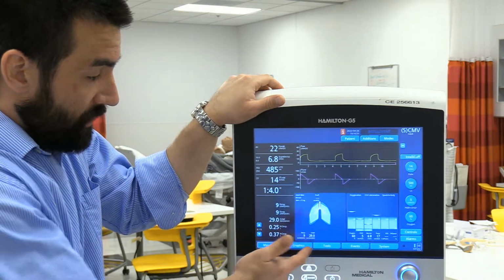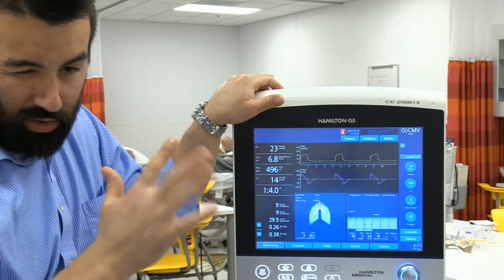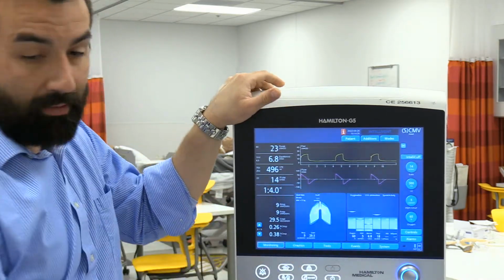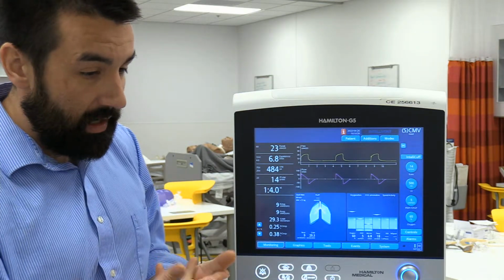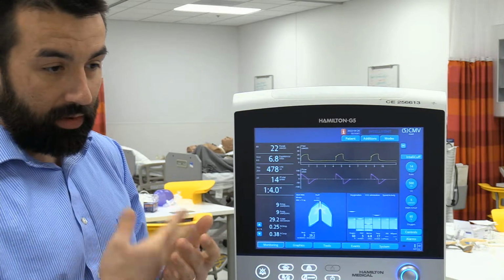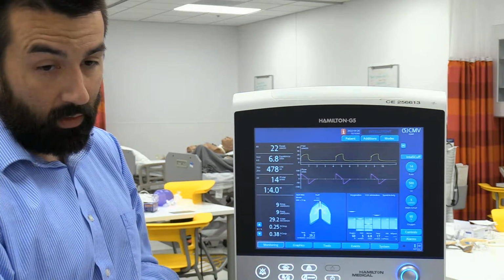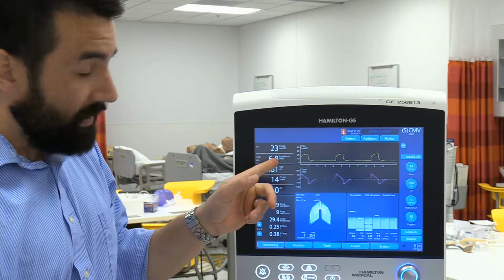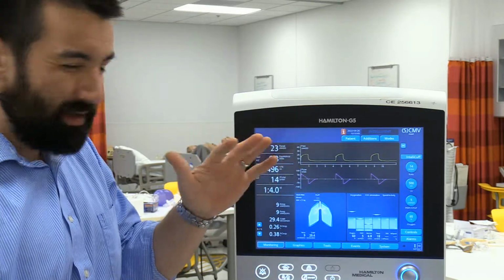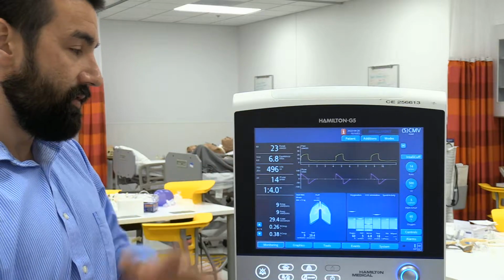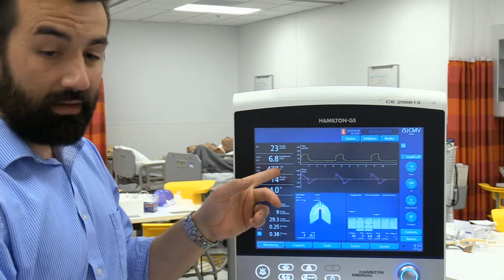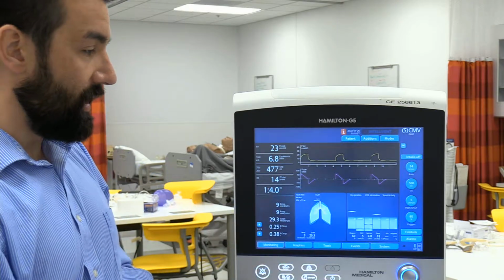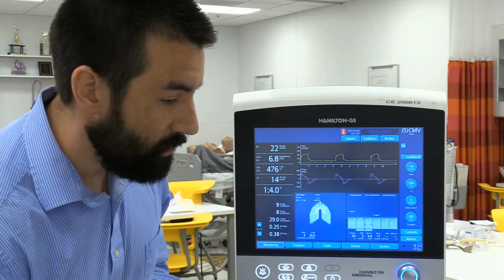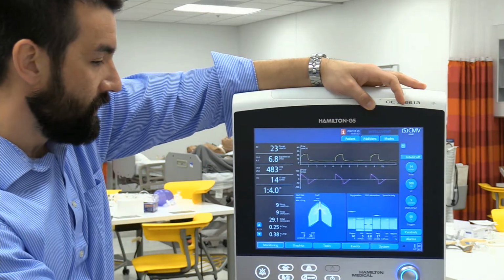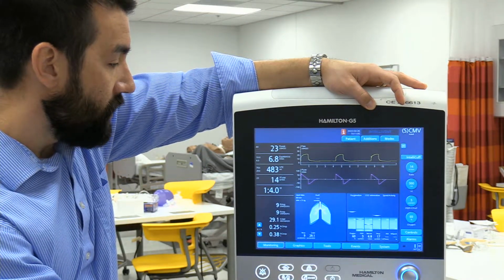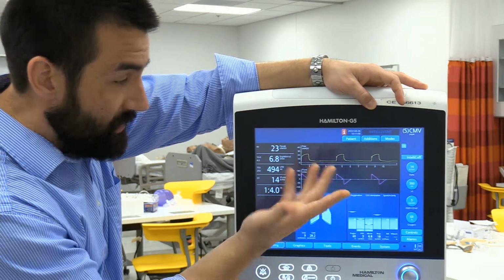So I'm going to show you how to get a plateau. Right now, 22 to 23 centimeters of water is what it's taken to deliver this tidal volume and overcome airway resistance, lung compliance, chest wall compliance, resistance going through our ET tube, all those different things. So that's the total in volume ventilation here. You can see my minute ventilation, what I'm expiring, is a little bit short of what I was looking for, around 7 liters a minute. That's just because our exhaled tidal volume is a little bit short of what's coming back here, and that's okay. I didn't do my pre-use check with my HME, so that could be a little bit of unintended dead space, and that's totally fine. So we get a blood gas in 30 minutes and check all that stuff.